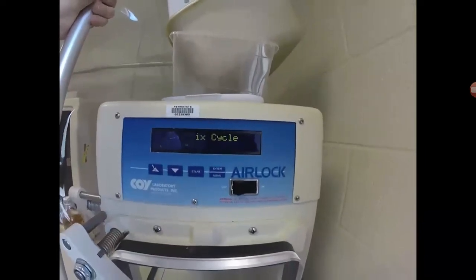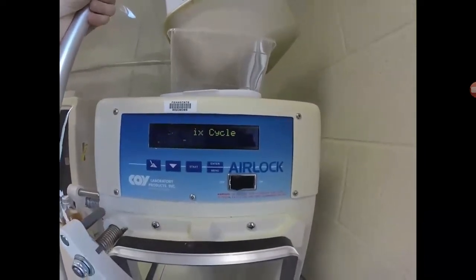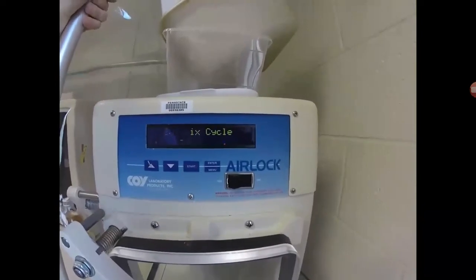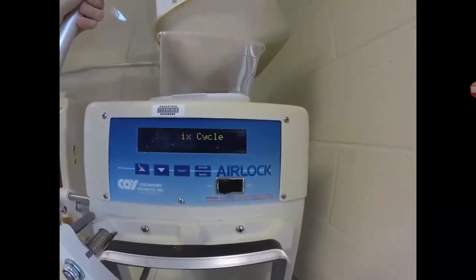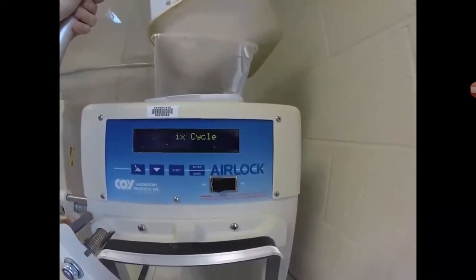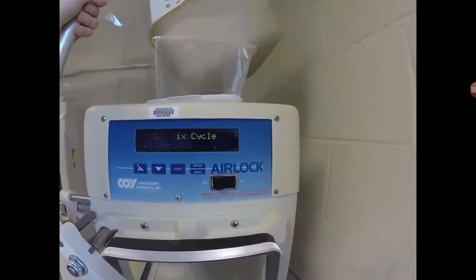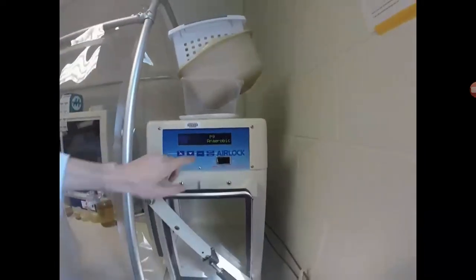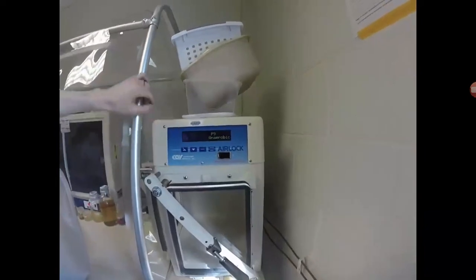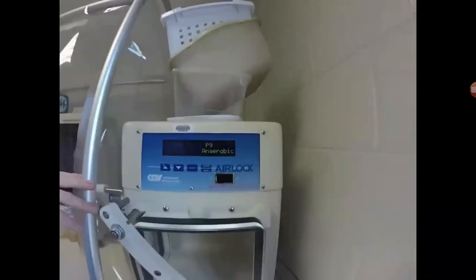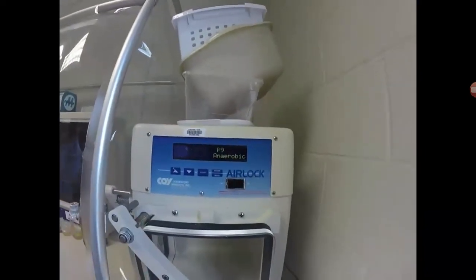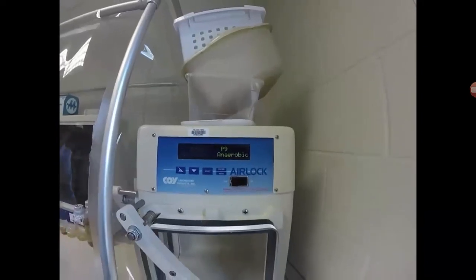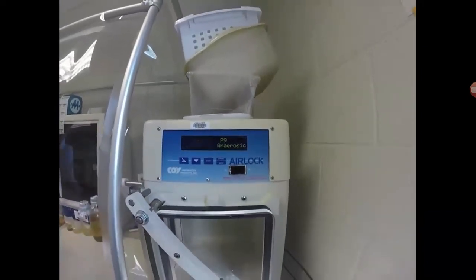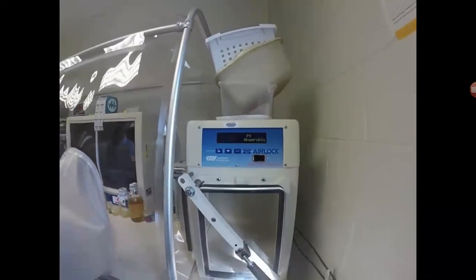So this is the final cycle. At the end of the cycle, it will beep. Once it reaches no vacuum. Okay, so it beeped. And now you can see this says anaerobic. Before it said aerobic, now it's anaerobic, meaning that it's relatively oxygen free inside of there. So at this point, you obviously don't want to open the outer door, or else you have to do the whole thing over again. But we can open the inner door.